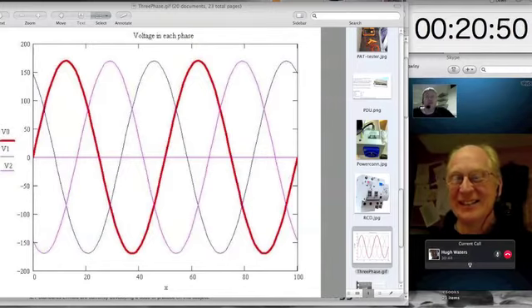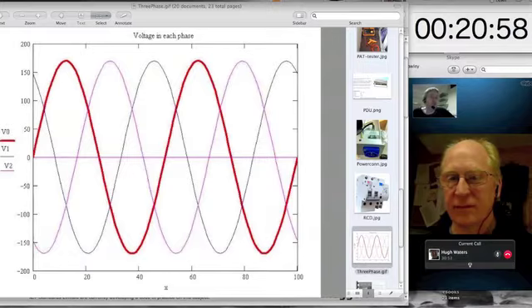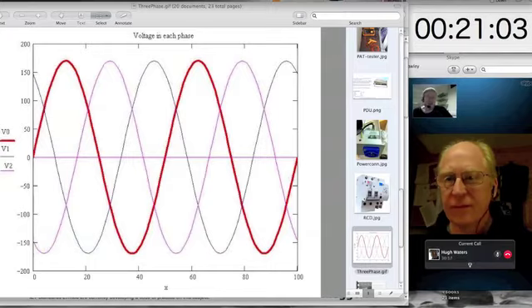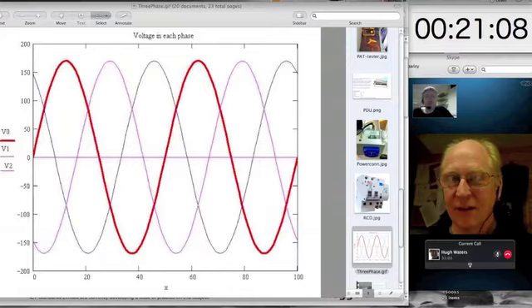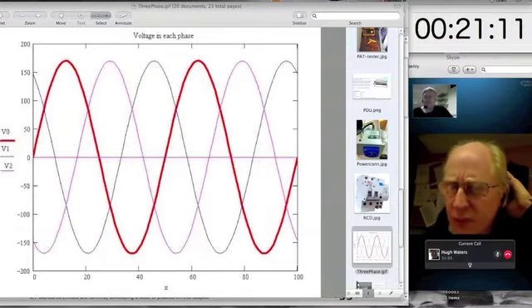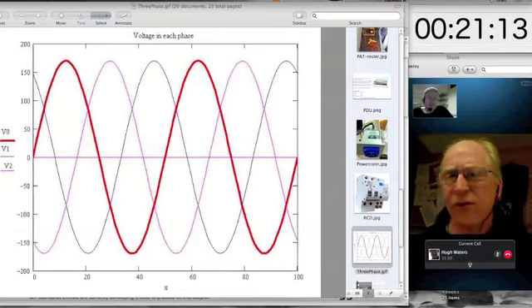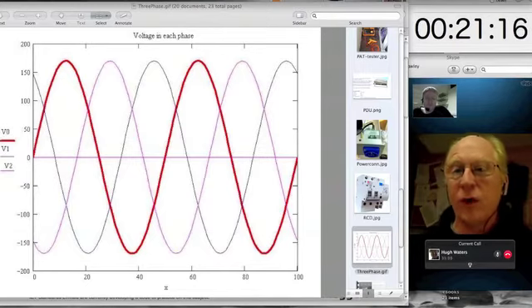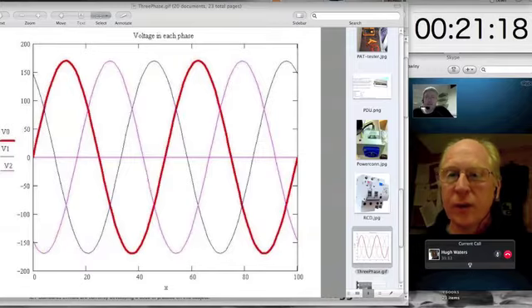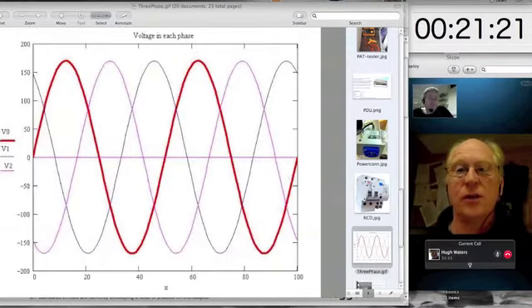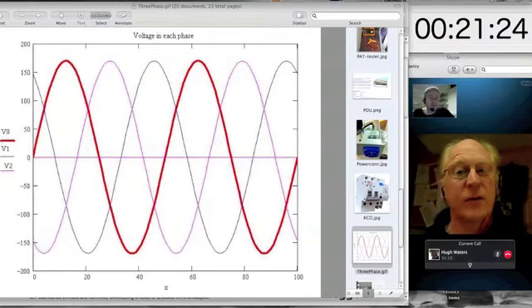And it was all because we had the studio lighting grid and the main machine room on the red phase. The edit suites and the domestic mains were sitting on the blue phase, and just general lighting was on the yellow phase. So, at some point, an electrician had made that decision: oh, that must be the best phase to put all this technical gear on. But of course, we were scared of putting stuff, certainly that it might be reached, on more than one phase. We built all our machine rooms so that everything, as far as possible, was on the same phase. We were terrified that you would have 2 phases within reaching distance.